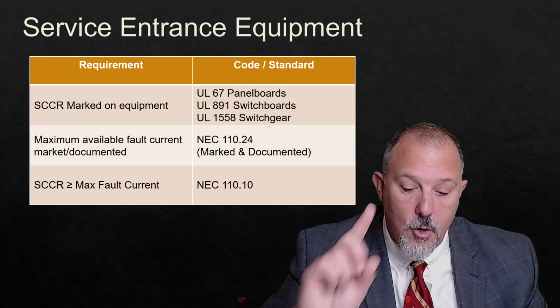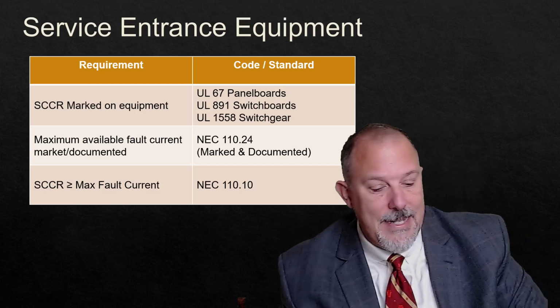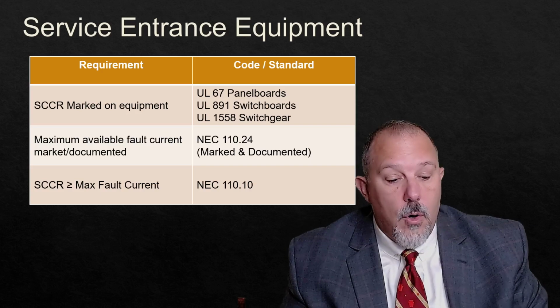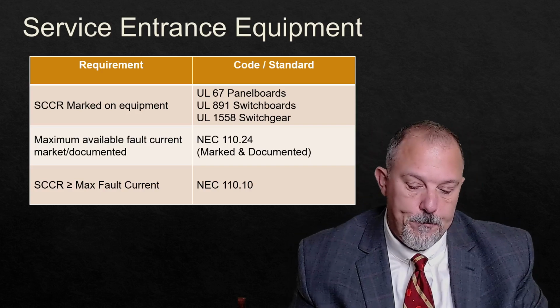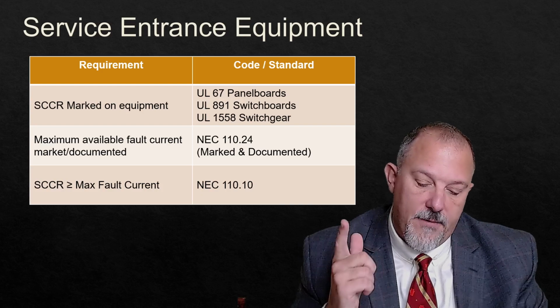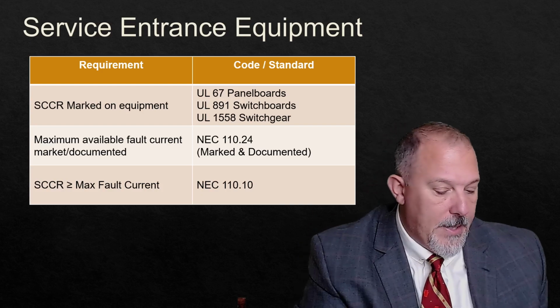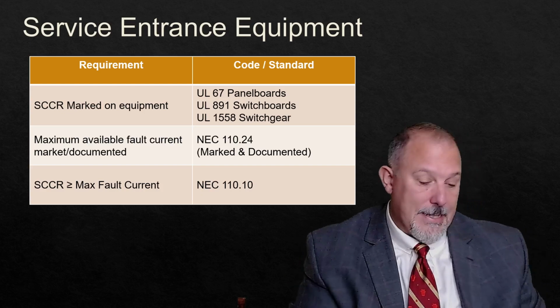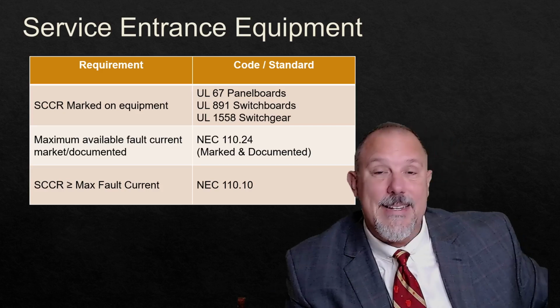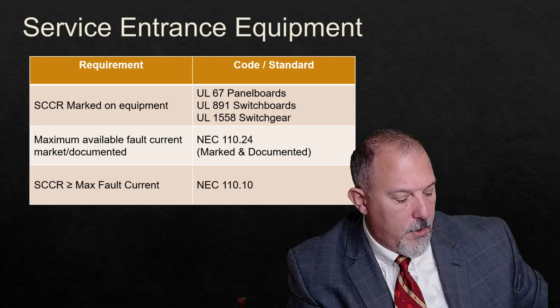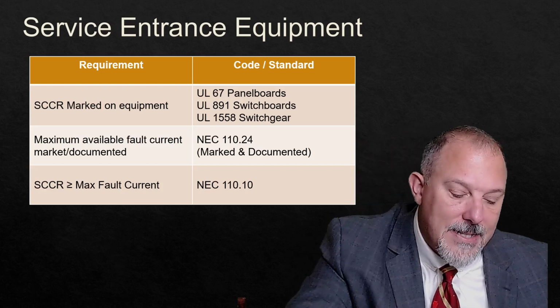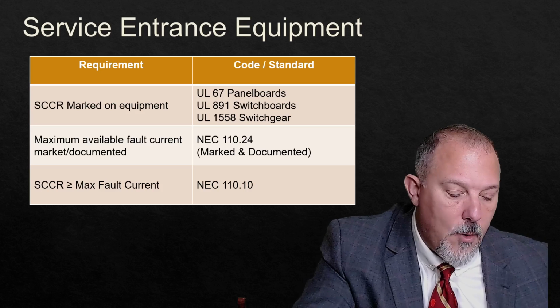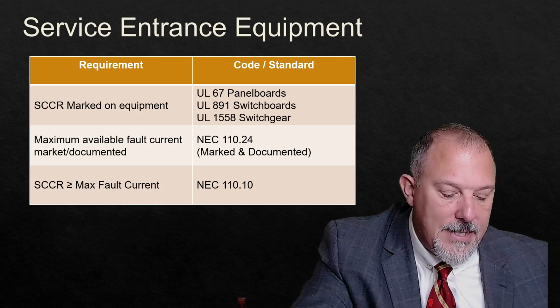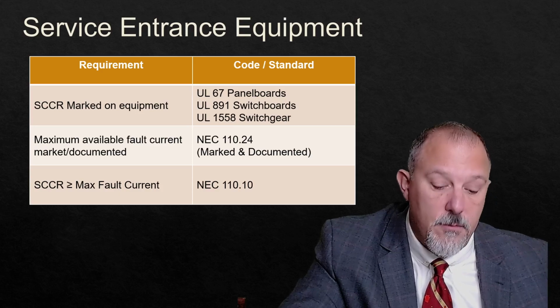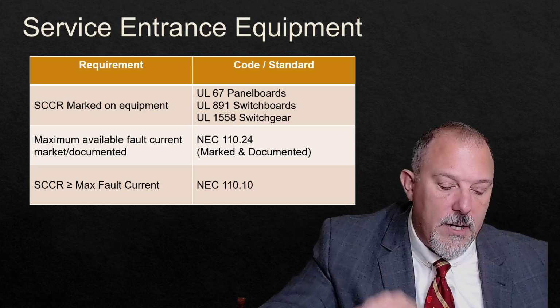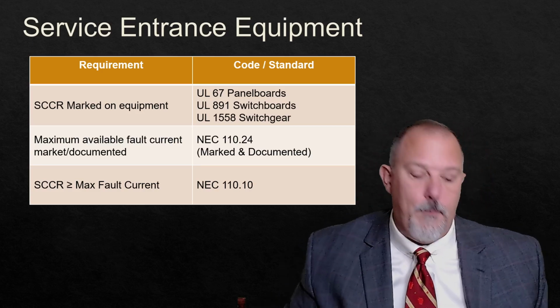110.10. Now, 408 in the 2020 version did add something. If it's a panel board, switchboard, or switchgear, I've got to find it. I should have put the reference up there, but I did not. Look at that. It's like it automatically opened there. 408.6. It says switchboard, switchgear, and panel boards shall have a short circuit current rating not less than the available fault current. In other than one and two family dwelling units, the available fault current and the date the calculation was performed shall be field marked on the enclosure at the point of supply. The marking shall comply with 110.21B.